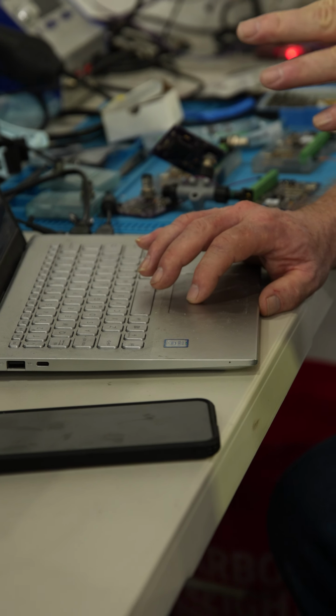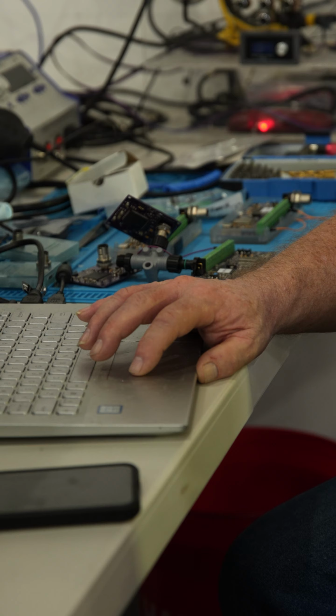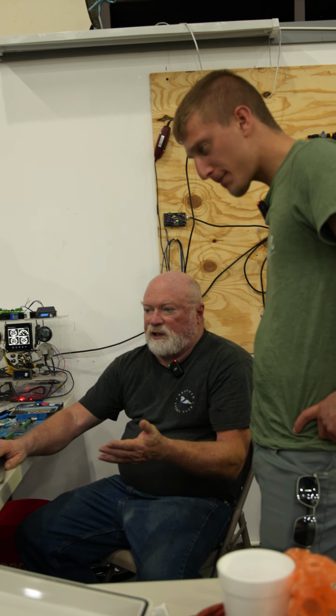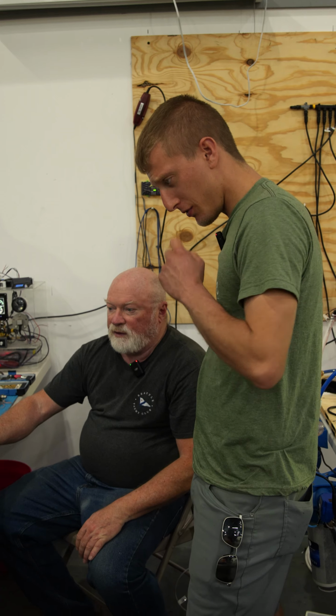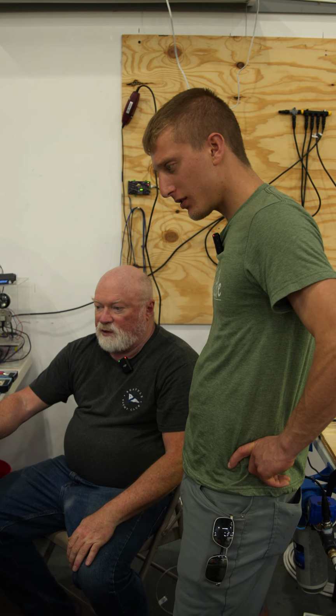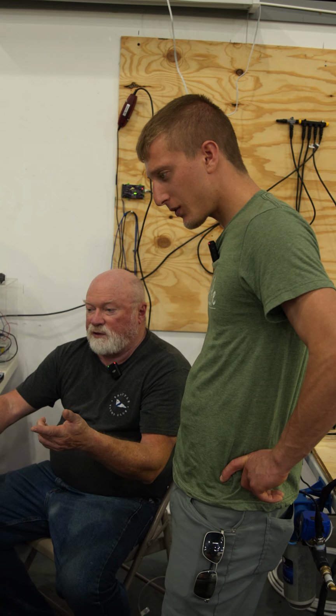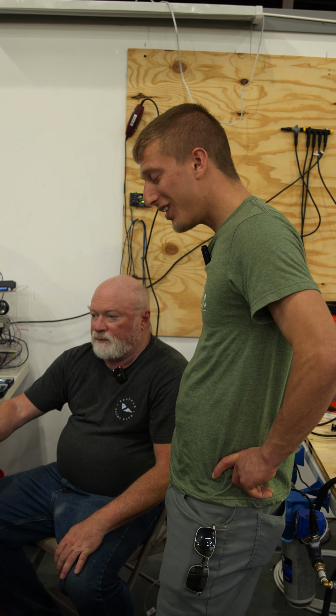This is not fully set up yet because we're just setting up the lab. Gallons to make. You can make water by volume or by time. And your flush timer, 5 days. Right now it's off, but every 5 days it'll flush itself. And it tells you when the next flush cycle will be. You can set what time of day you want it to run. And then these are the maintenance compressor hours and minutes and days, and the filters also.